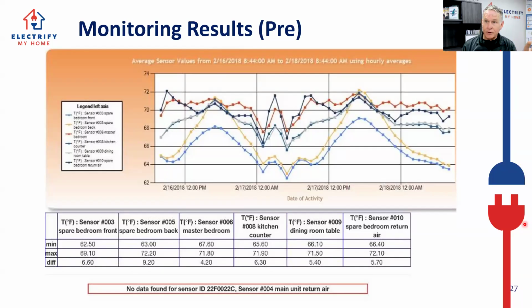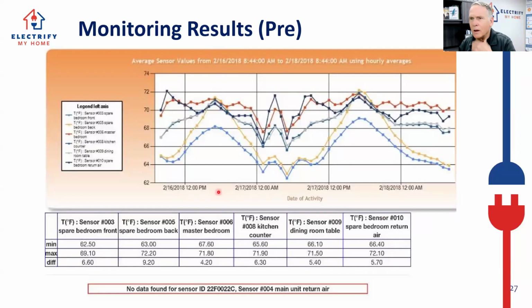These are all thermometers. And we're looking at supply and return temperatures, like, let's see, that light blue temperature. The spare bedroom's front is the supply temperature here. And you can't see where I'm pointing at my screen. Down here, this is the bedrooms. This up here is the master bedroom, or the spare bedroom return air, but it doesn't matter. You wouldn't want to live in a house that was this uncomfortable. I'm getting spreads here all the way from 72 degrees to 62 degrees. This is like a 10-degree differential coming around in this house.